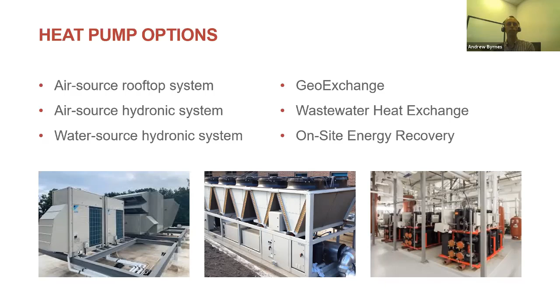Another example is on-site energy recovery. Heat pumps can be used to recover energy within a building. If there's air conditioning on one side and heating on the other, a heat pump is a perfect solution because it produces both a cold and a hot side—the cold for the air conditioning load, the hot for the heating load—making it a very efficient way of moving heat around within a building.